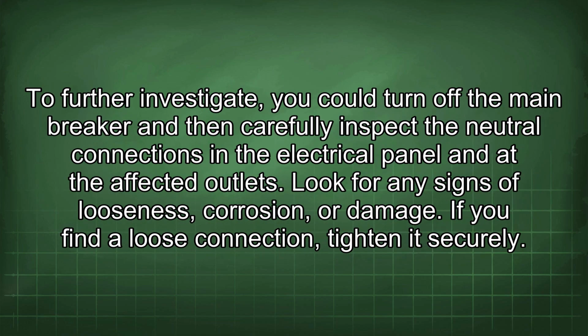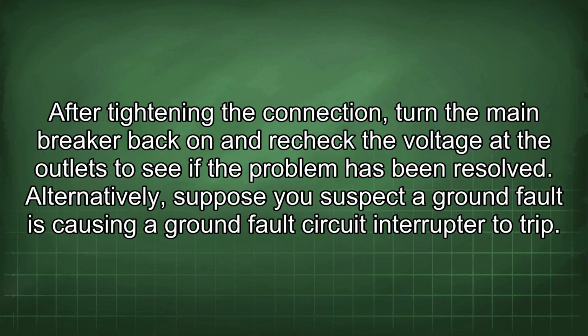To further investigate, you could turn off the main breaker and then carefully inspect the neutral connections in the electrical panel and at the affected outlets. Look for any signs of looseness, corrosion, or damage. If you find a loose connection, tighten it securely. After tightening the connection, turn the main breaker back on and recheck the voltage at the outlets to see if the problem has been resolved.